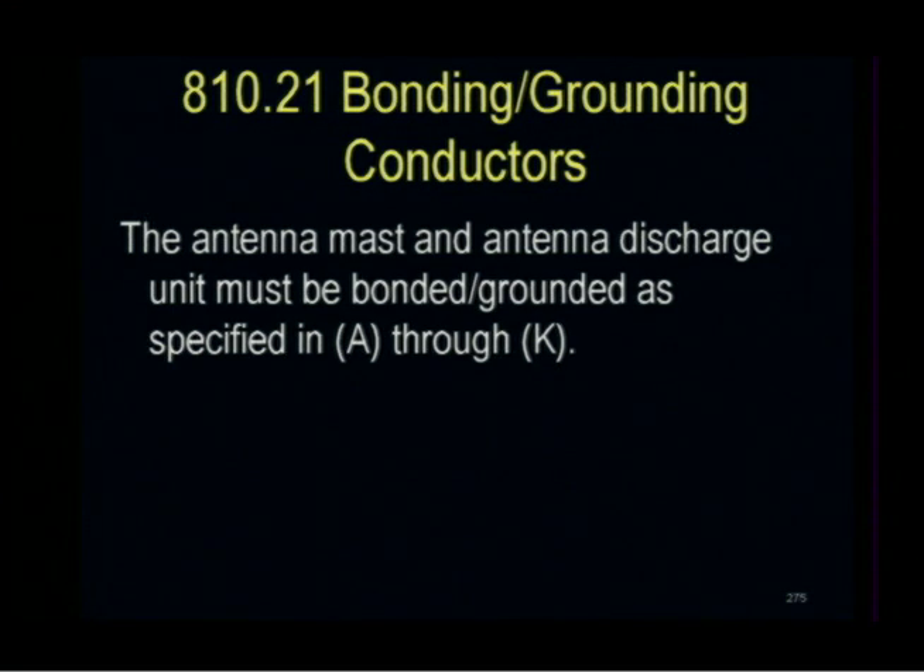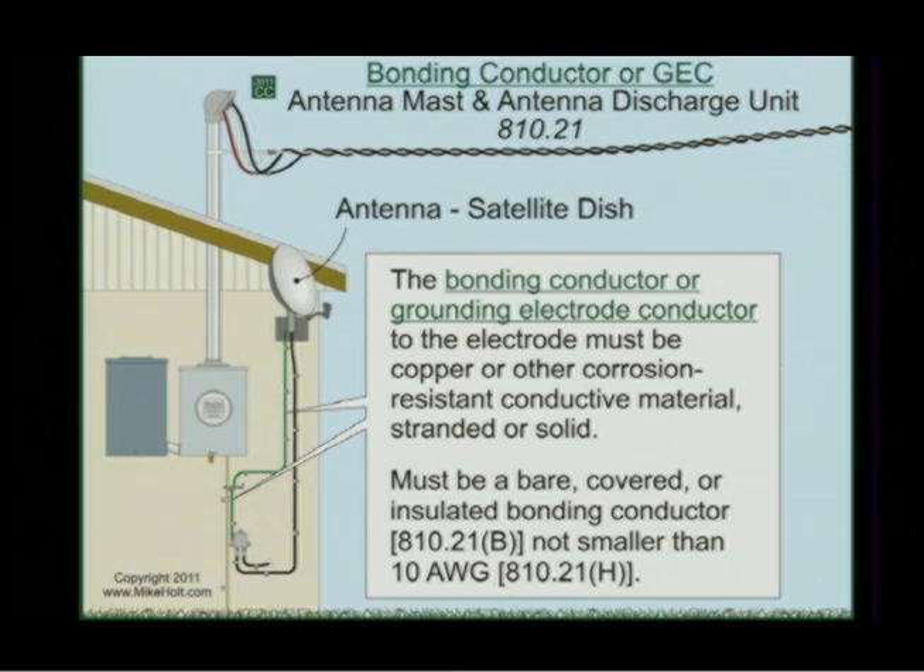The antenna mast and the antenna discharge unit must be bonded or grounded in accordance with Article 810.21A through K. The bonding conductor or the grounding electrode conductor to the electrode must be copper or other corrosion-resistant material. It must be bare, covered, or insulated.